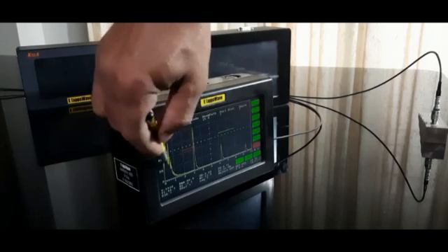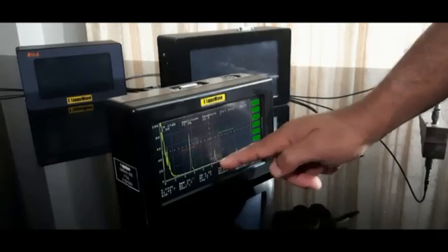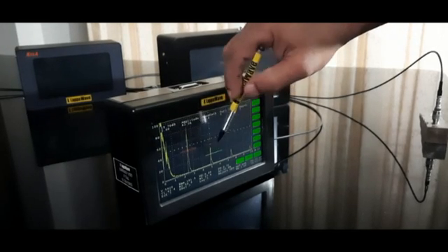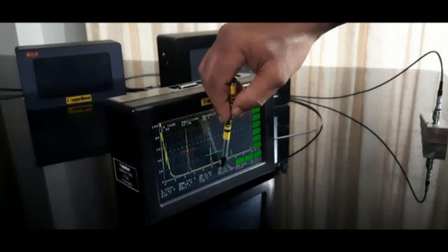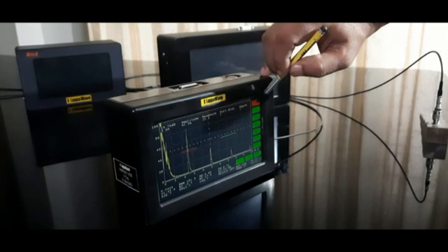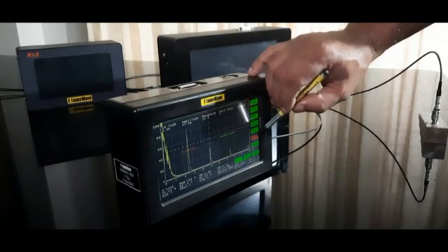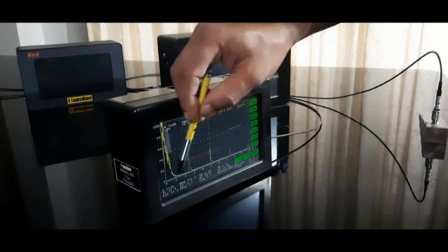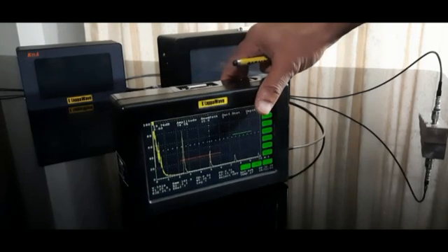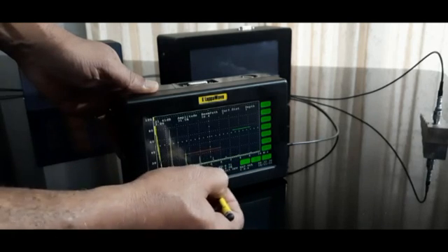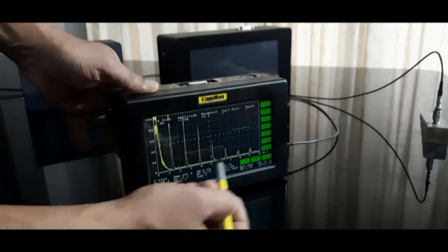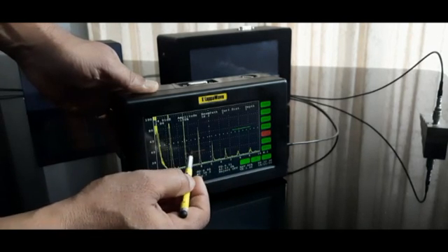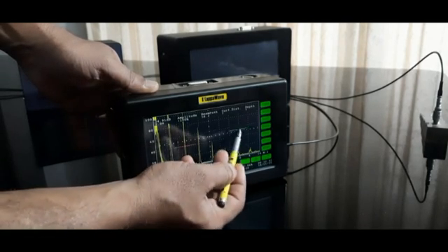It's very easy to use. Amplitude can be changed by dragging the vertical scale, or range can be changed on the horizontal scale. This model is supplied with DAC, TCG and DGS, and it's a proven model in the field. Both the gates are active, and a single gate can be extended to cross two indications to give you an echo to echo value. Constructing DAC, TCG all becomes quite easy with this instrument. Gates can be easily moved anywhere on the screen.